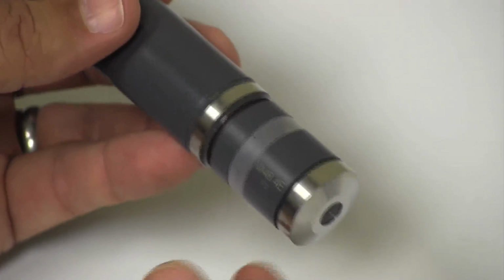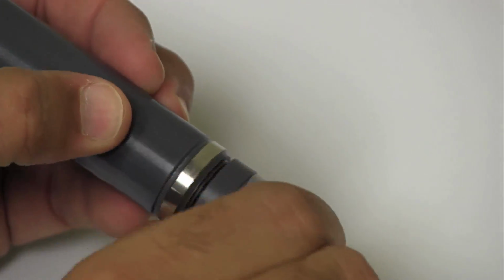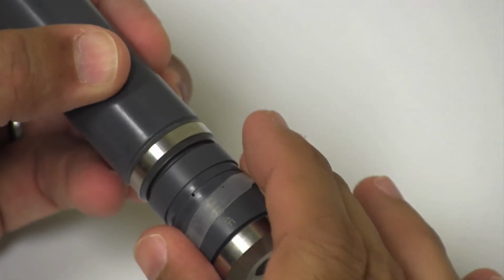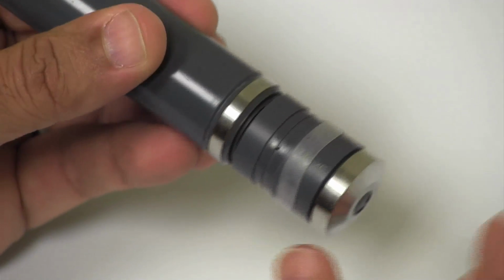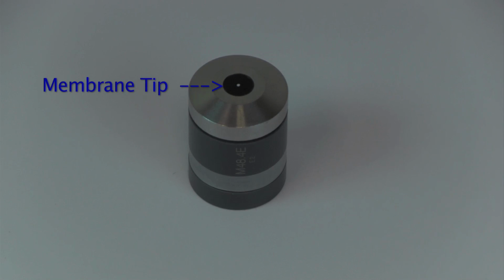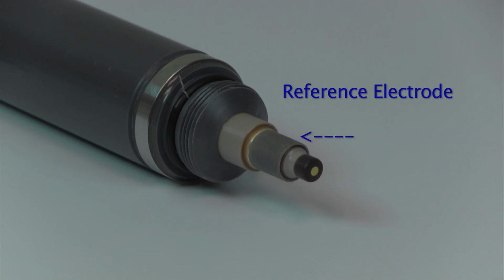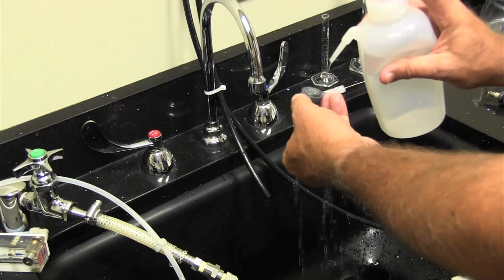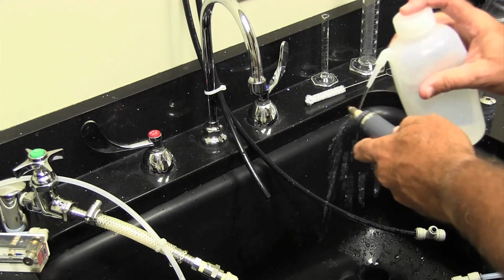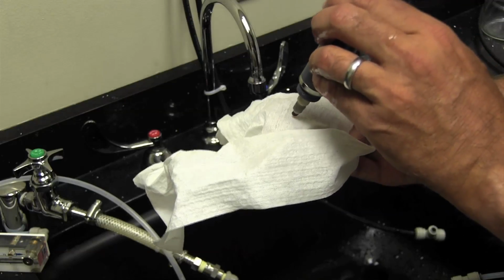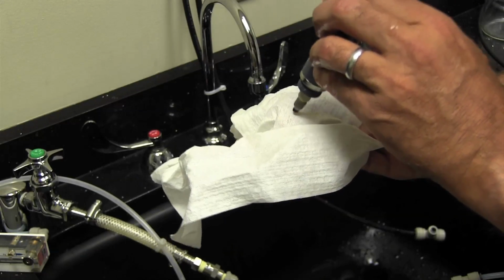Before a membrane cap is ever removed, it is critical to slide the elastic seal away from the tiny vent hole. Failure to do so can result in permanent damage to the membrane. Also, do not touch the membrane surface, which is located on the tip of the cap, or the gray-colored reference electrode. It is okay to rinse these surfaces to flush away any old electrolyte, and then use a paper towel to dry the gold tip of the working electrode.